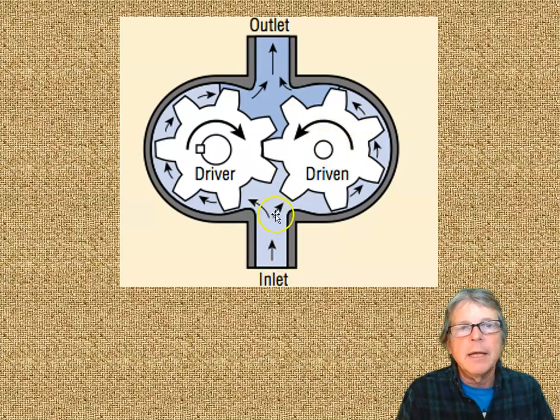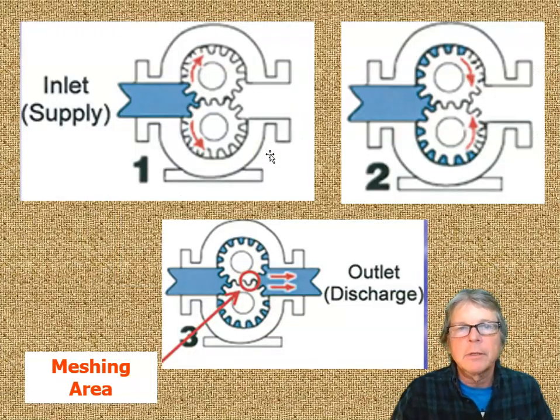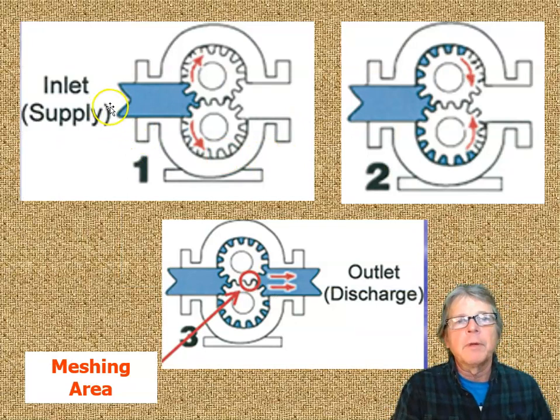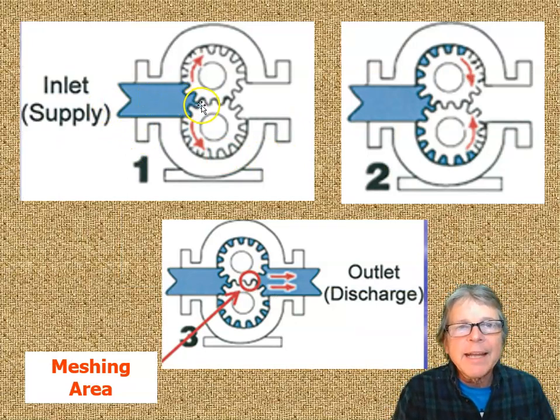The engine is driving this gear, so fluid goes either left or right. Some goes left between the teeth. Here's our inlet, number one. The colored blue comes in here. It can't go down the center—these gears are squeezed together. That's blocked off. The opening for this fluid to fit through is between the teeth.